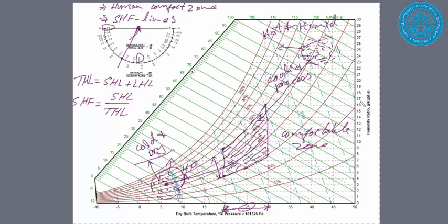In other words, if I have a process on the psychrometric chart straight up or down vertically, it shows me the sensible heat factor is zero. And if there is a horizontal process, it shows the sensible heat factor is one.